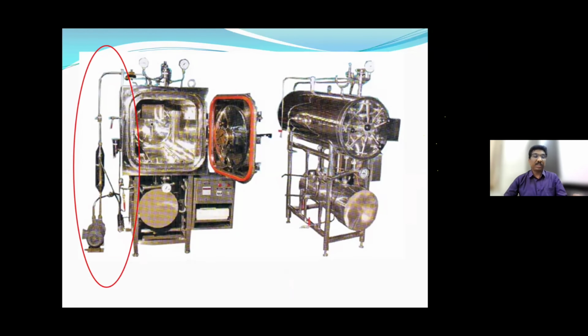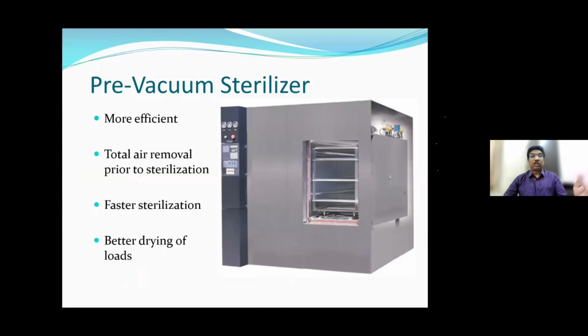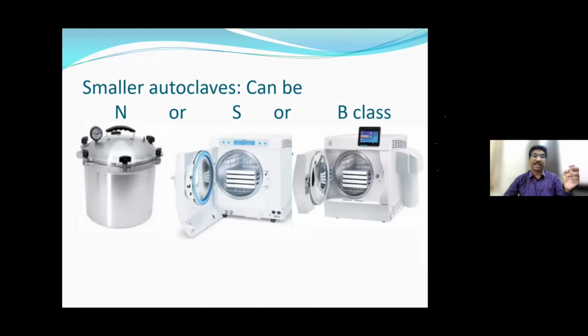Using this vacuum pump, the air inside the sterilizer is removed, turning this horizontal autoclave into a Class B autoclave. So you have these advanced kinds of sterilizers also, wherein they have more efficient air removal prior to sterilization, and they can also achieve faster drying times.